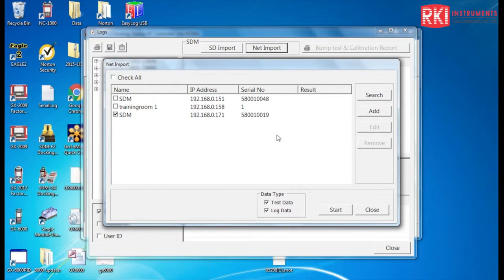So I'm going to go ahead and show you. Now that it's found the dock, I can select it. I'm going to select this one because this is the one that I have connected. And if I want to bring in the data, I can bring in either bump test and calibration data, or I can bring in log download data, or I can bring in both. If I click the start button, it'll bring the data in. It'll tell me that it's communicating with that dock. And it tells me that I brought in 5 files. I can view those files now if I go back to the normal log sorting.